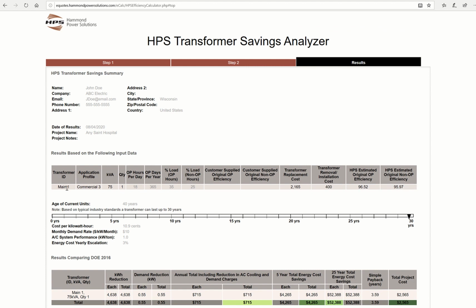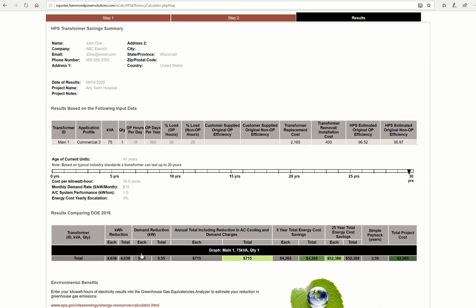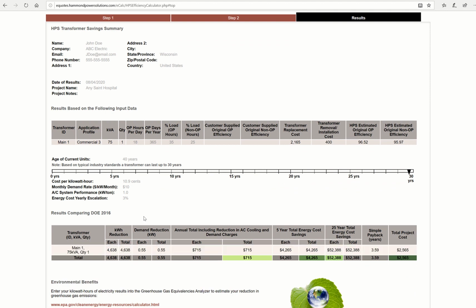In this case, we're saying that the main 75 kVA transformer, based on the application profile of Commercial 3 — and again, you can put your own profile in here if you want, but we're just using the pre-built one — is going to save approximately 4,638 kilowatt hours per year. It's going to have about a 0.55 kilowatt demand reduction, and it's going to save approximately $715 in its first year.